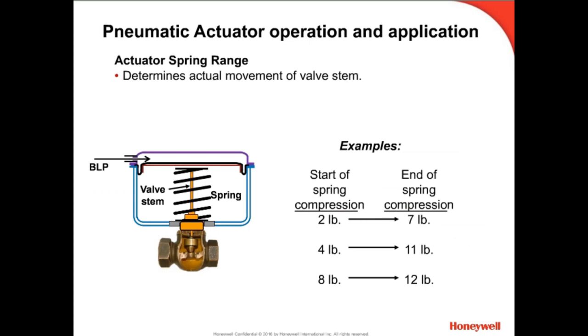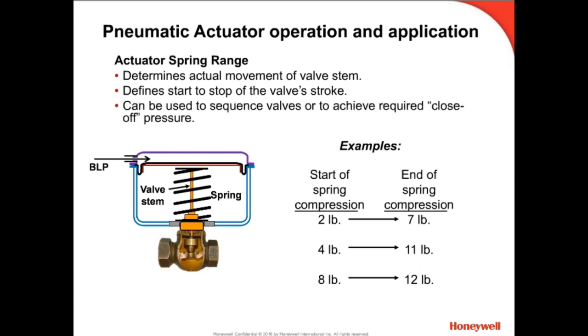Pneumatic actuators will always have a listed spring range. The spring range determines the pressure change required for full movement or stroke of the actuator from open to closed or closed to open. As an example, if this valve has a 4 to 11 spring range, then at 4 pounds the valve is full open. As the branch line pressure is increased, the valve moves towards the closed position, and at 11 pounds the valve will be fully closed. Thus, the spring range of a valve defines the start and stop of the valve stroke.